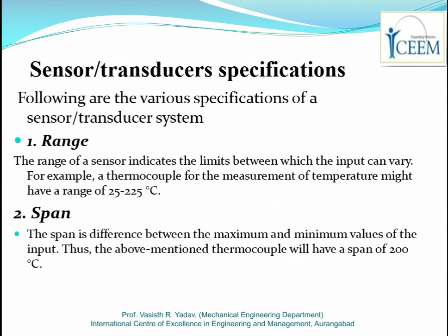The second specification is span. A span is the difference between maximum and minimum values of the input. Since we said in our previous example that a thermocouple has a range of 25 degrees to 225 degrees Celsius, it can measure a minimum temperature of 25 degrees Celsius and a maximum temperature of 225 degrees Celsius. So its span becomes maximum minus minimum input level. So 200 degrees Celsius is the span of our previous thermocouple which we used in our example.